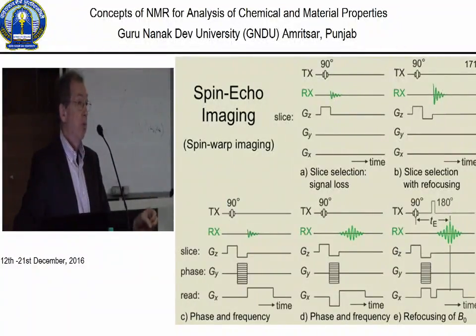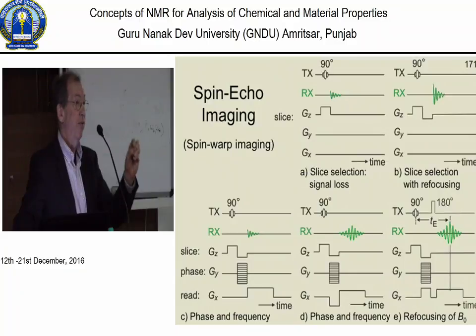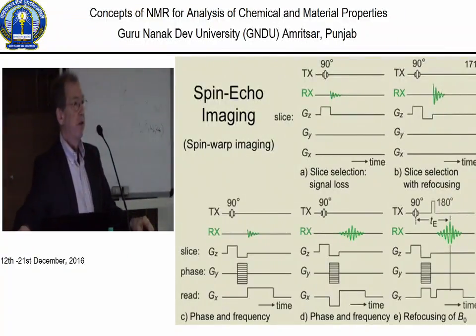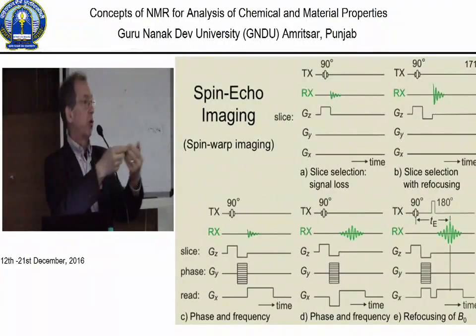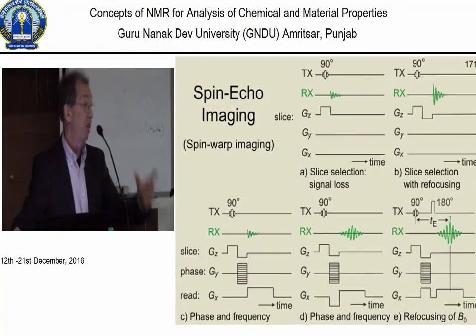You want to do imaging because you want to see structures in your object. When you have structures in your object, it means that each structure has a different magnetic susceptibility, how it takes up the magnetic field, than the other structures next to it. But when that is different, it's the same as you have two materials next to each other that have different refraction index in optics. So the magnetic field gets distorted at the interface and becomes inhomogeneous inside the object, because the material is inhomogeneous. So these are effects that lead to distortions and degrade your image resolution.